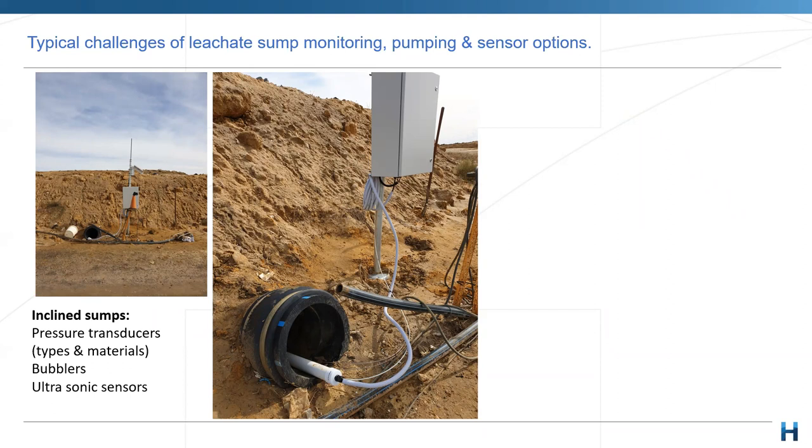Yeah, sure. So I think one thing worth highlighting is the benefit of actually having a telemetry system attached to a level monitoring setup. So yes, there are a few types of level sensing devices, in terms of using bubblers or submersible transducers or some kind of sonic device. They all have an output that can be used by a logger box.